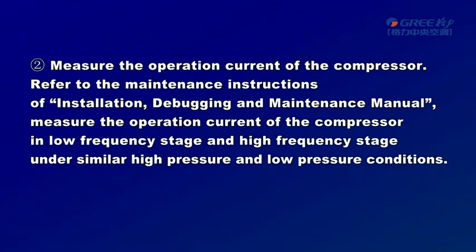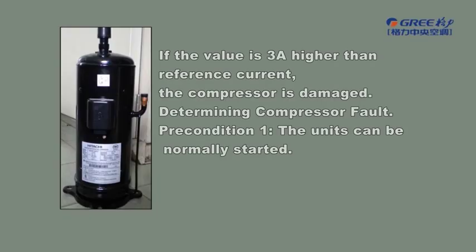Measure the operation current of the compressor. Refer to the maintenance instructions of the installation, debugging, and maintenance manual. Measure the operation current of the compressor in low frequency stage and high frequency stage under similar high pressure and low pressure conditions. If the value is 3A higher than the reference current, the compressor is damaged.